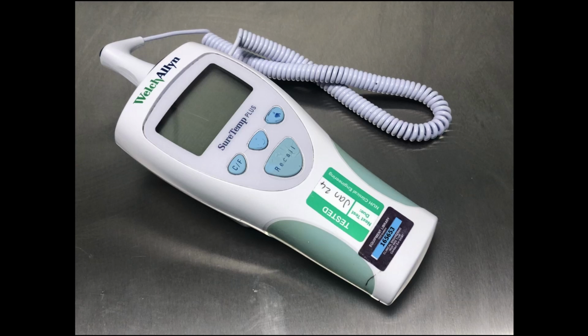In normal mode, the temperature is measured at discrete intervals and then calculates a rate of change according to a proven algorithm, and this allows the thermometer to predict the endpoint it would reach if it were left in the mouth until the mouth temperature was reached. This predictive feature allows the thermometer to arrive at an accurate oral temperature reading in approximately 4 seconds. And for axillary mode, it can reach that predicted algorithm in 10 seconds.